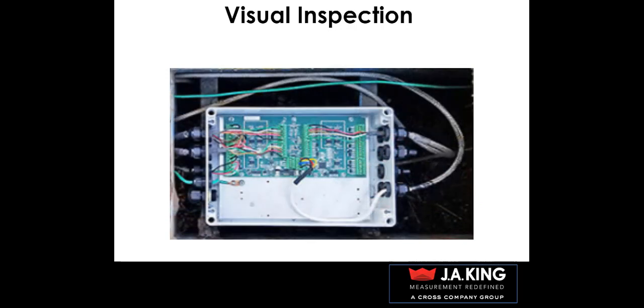Check the connection of the summing box to the digital indicator. Check the excitation voltage source connections. Ensure the excitation voltage source provides a stable signal. If visual checks reveal issues, correct these issues and determine if faults persist. If they do, proceed with troubleshooting the load cell.